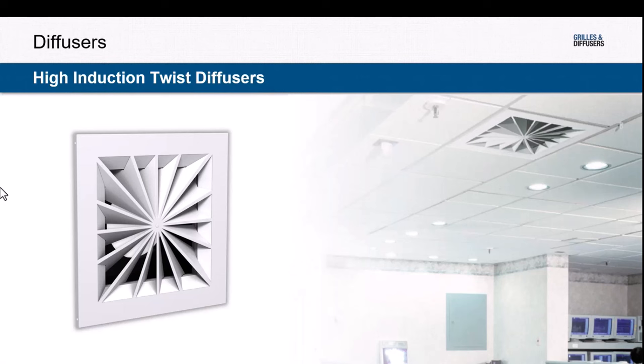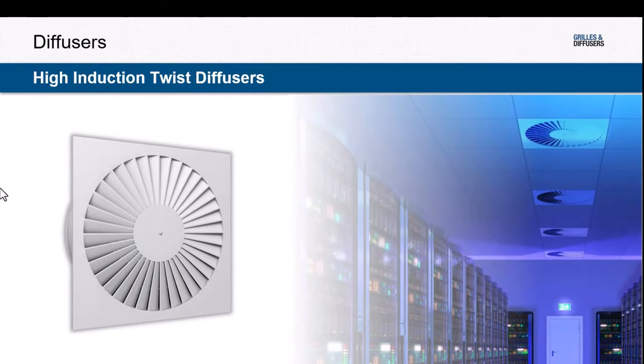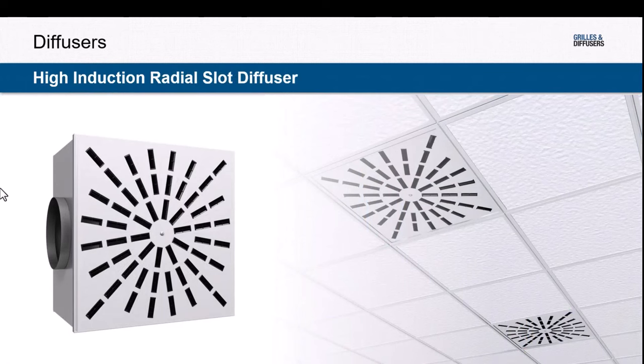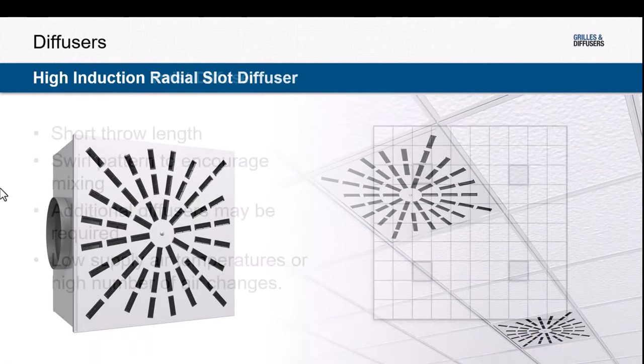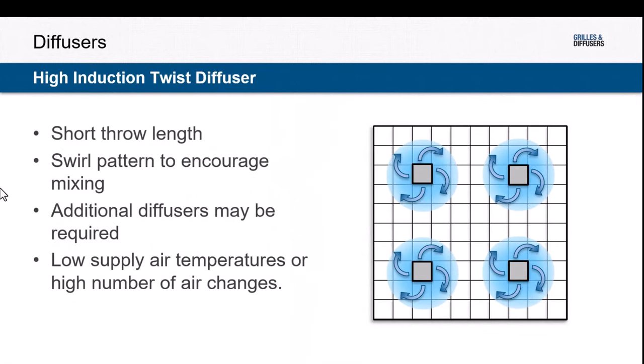High induction twist diffusers are sometimes selected because of their unique appearance, but beyond that they have a very specific throw pattern — a swirl or twist pattern. This type of diffuser ends up with a shorter throw length because of the swirling, turbulent flow, and it encourages mixing within the room. One application is where there are high loads and we're delivering high air volume where shorter throw lengths are desirable. If the supply air temperature has a high delta T, the twist pattern can help get that supply air temperature closer to room air temperature faster.